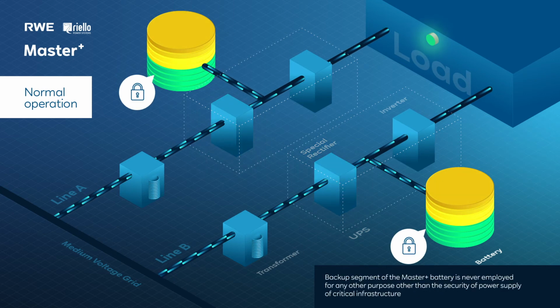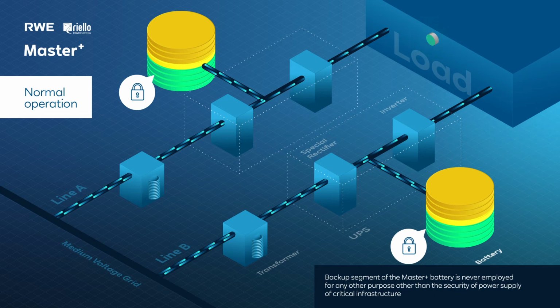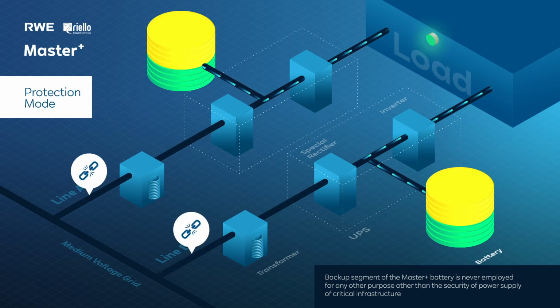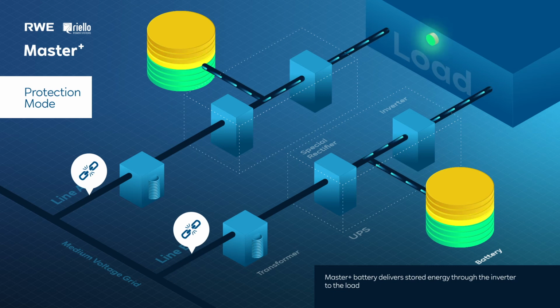The backup segment of the Master Plus batteries is always ready to be used in case of any power supply problem. It is never employed for any other purpose other than the security of power supply of your critical infrastructure. In case the power supply is in danger or not within the permitted range, Master Plus switches to protection mode, instantaneously supplying the energy stored in the batteries through the inverter into the load.